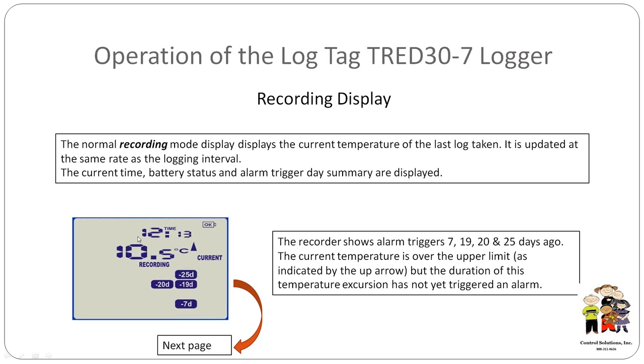So on my display here, I have a time of 12:13. My battery's okay. I'm displaying a current value of today. The last reading that I took, the arrow is going to tell me I was too hot, and I have a 10.5 Celsius. The log tag is going to enable you to have an alarm delay. So if for some reason you open the door and you were doing inventory, we're going to give you a grace period before it actually triggers it. So the other days down here say 7 days ago, 19 days ago, 20 days ago, and 25, I had an alarm condition.